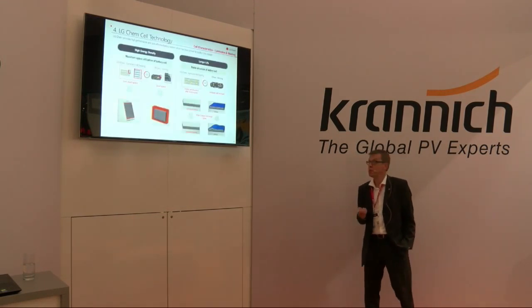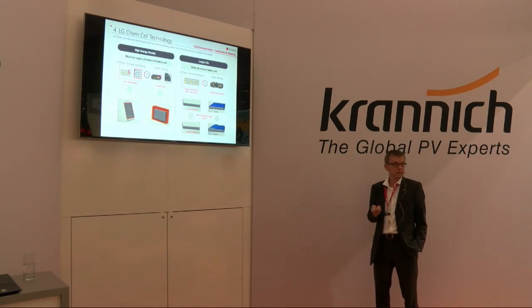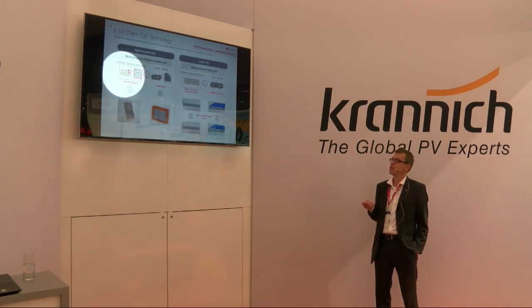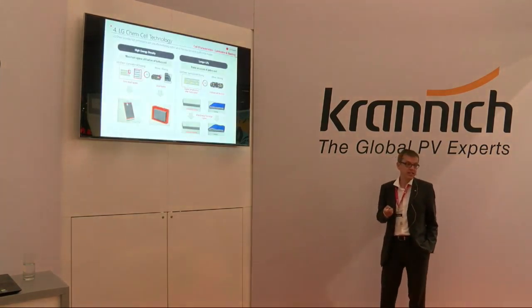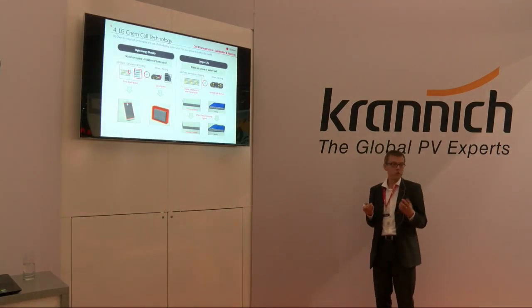I would like to talk a bit about the cell technology. The core product of LG Chem is a pouch cell. A pouch cell means we are using stacked and laminated cells, anode, cathode, and the cell chemistry is put into cell stacks and then put into a vacuumized pouch cell. This results in high energy density, and if the cell works, which means energy is stored in and taken out of the system, there is usually some heat generation inside the cell, and the whole cell heats up.